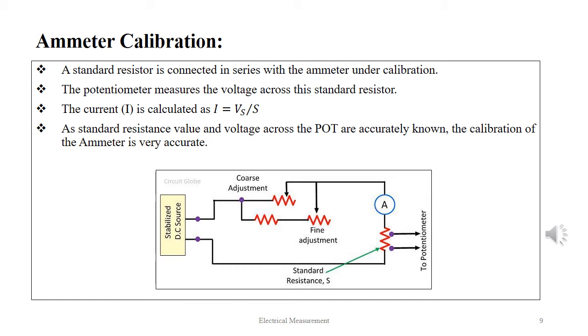Another very important device in electrical measurement is the ammeter, used to measure current. A standard resistor is connected in series with the ammeter under calibration, as shown in the picture here. The potentiometer measures the voltage across this standard resistor S, and the current is calculated by the formula I equals Vs by S, where I is the current through the circuit and Vs is the voltage drop across the standard resistor. As the standard resistance value and the voltage across the pot are accurately known, the calibration of the ampere meter, that is ammeter, is very accurate and very precise.